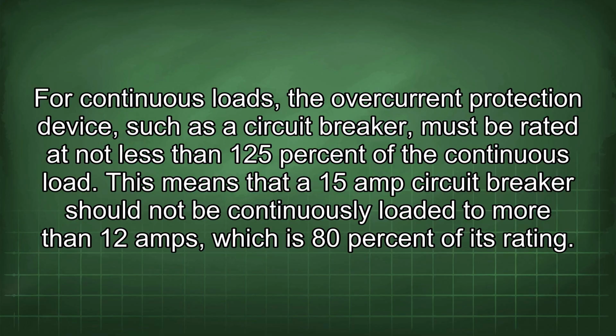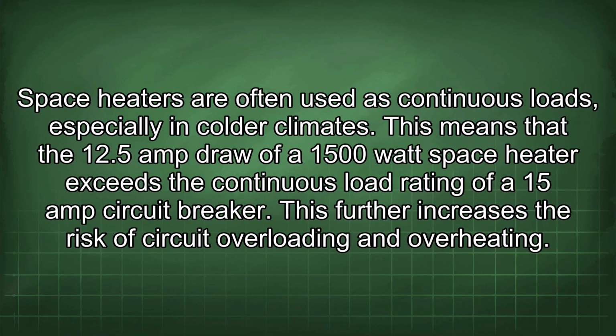This means a 15 amp circuit breaker should not be continuously loaded to more than 12 amps, which is 80% of its rating. Space heaters are often used as continuous loads, especially in colder climates. This means the 12.5 amp draw of a 1500 watt space heater exceeds the continuous load rating of a 15 amp circuit breaker, further increasing the risk of circuit overloading and overheating.